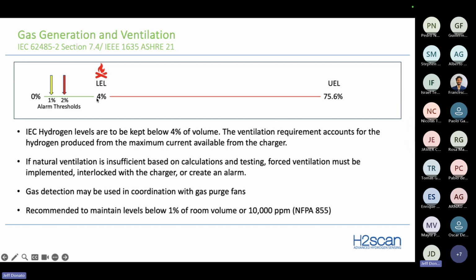And like I said before, the IEC basically says that we have to keep below 4%, but a lot of documentation doesn't necessarily say where we should set our alarm thresholds. So the NFPA 855 came out with, we really need to set it at 1%, so we have enough time to deal with any kind of mitigation strategy before it gets to the explosive level.